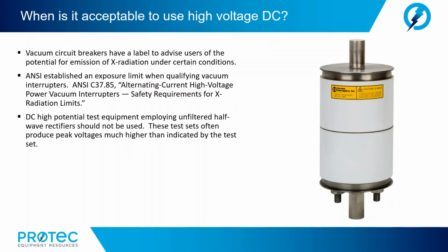Now, where this information becomes important is when testing vacuum integrity with a DC high potential test set. You need to know your test set and its design. It is important that DC high potential test equipment employing unfiltered half-wave rectifiers not be used in this application. These test sets often produce peak voltages much higher than indicated by the test set. Therefore, the actual voltage applied to the vacuum interrupter by such test sets will be significantly higher than the voltage for which the vacuum interrupter is qualified. This in turn has two unfortunate consequences.